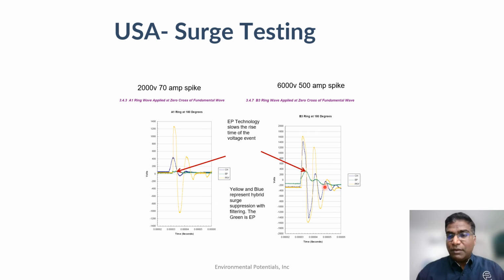If you don't have our patented waveform correction technology, we would be releasing the ringing noise back onto the system, but we are not. Look at this green line - we don't have any negative swing or positive swing left over after the unit is subjected to the transient.